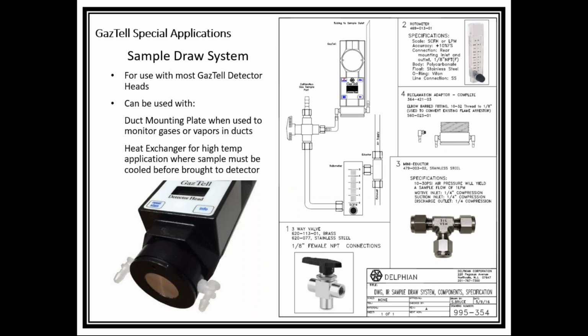When you're monitoring for gases in ducts or maybe an oven or something similar, the way to go is what we call sample draw. And the sample draw, as the picture depicts, is a sensor connected to a three-way valve, connected to a rotometer so you can adjust flow rate, connected to an eductor. An eductor is basically a device that uses the Venturi effect to, when you put shop air or any type of air on the one side, pull a vacuum on the other. And going through the eductor, eductors actually can suck up a very high volume of air. So when you use an eductor, you need a rotometer basically to control the amount of flow because you don't want too much sample coming out of your duct or your oven.